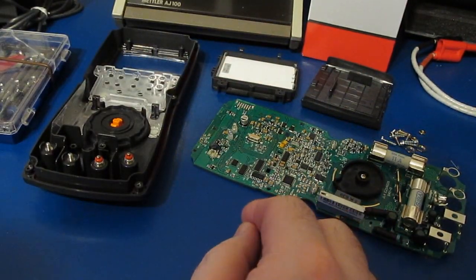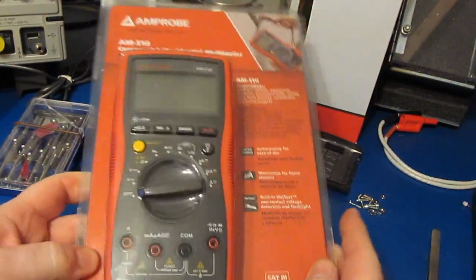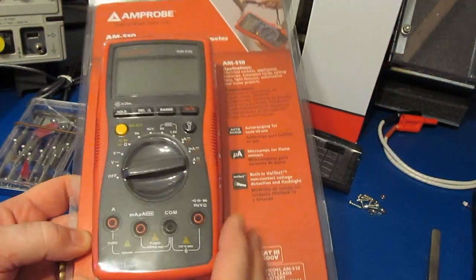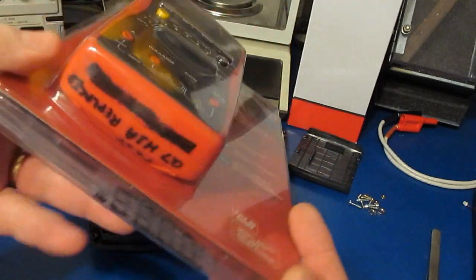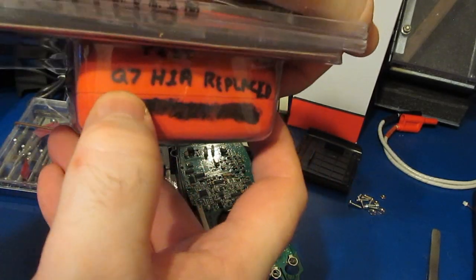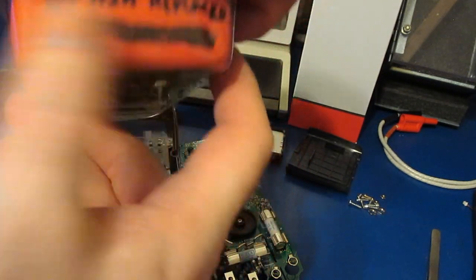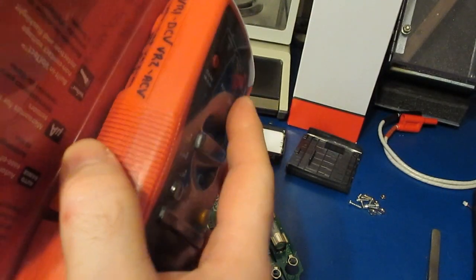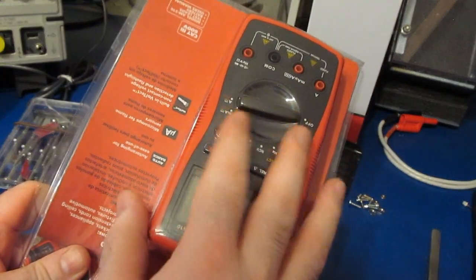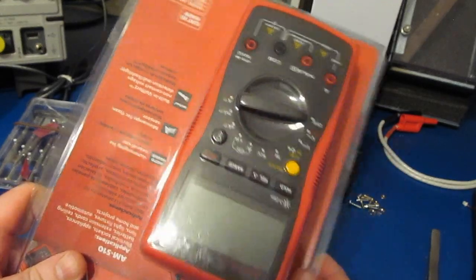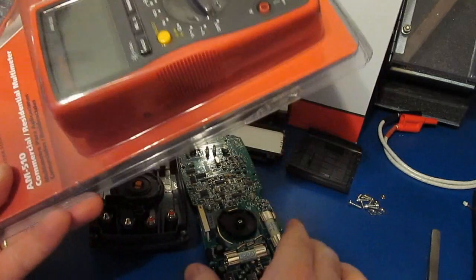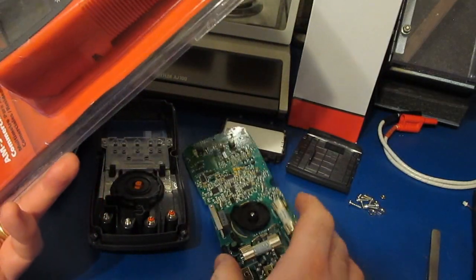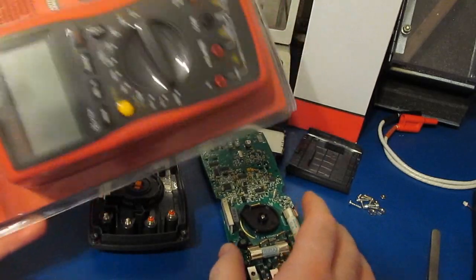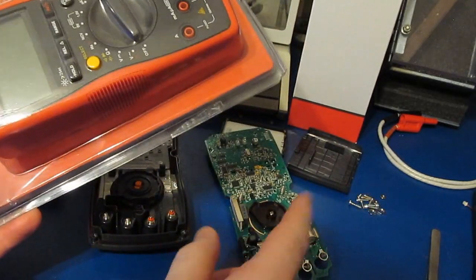So I'm very disappointed in the meter. Again, this thing cost over $600. Again, this Amprobe meter cost less than $50 and was the runner-up in my initial testing. And while I damaged it, you can see right here, Q7H1A replaced. So while it was damaged, I was able to repair this meter. And I've since gone back and transient tested this thing again at 5,000 volts. Handles it no problem. So the fact that you've got a company like Keysight who can't produce a meter at the cost of $600 that'll survive such a low transient, it's pretty discouraging.